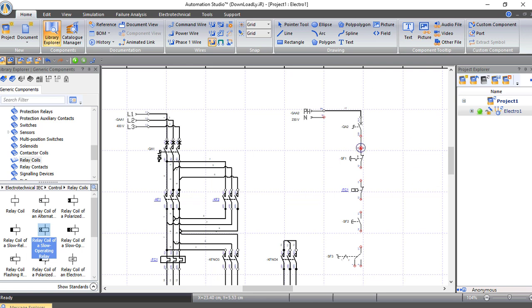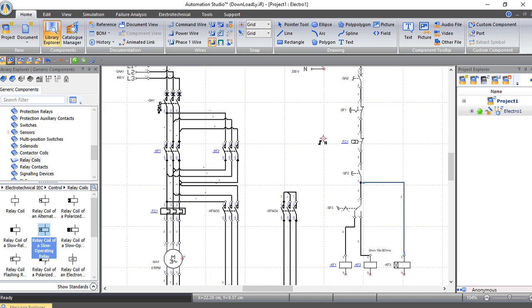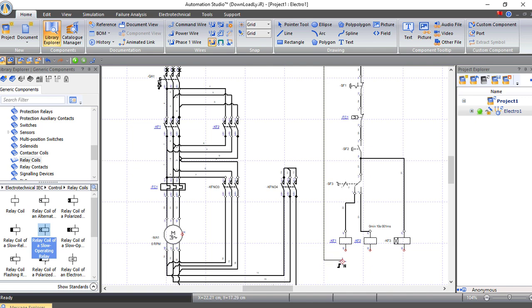Now let's start connecting our circuit. This is the line connected to the circuit breaker, then to the normally closed emergency switch, then to the normally closed contact from the thermal overload, then to the start switch, then to the selector. The selector will choose between K1 or K2. Also the power here will go directly to the timer to start working. Now let's connect the neutral to the other ends of the coils of the contactors.